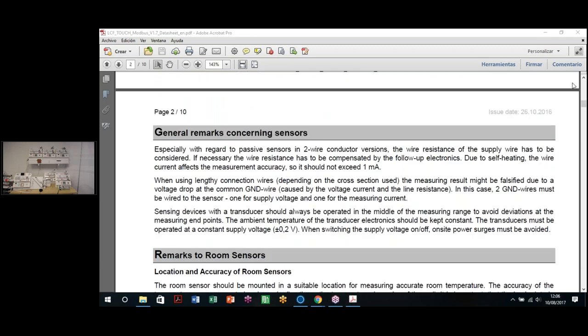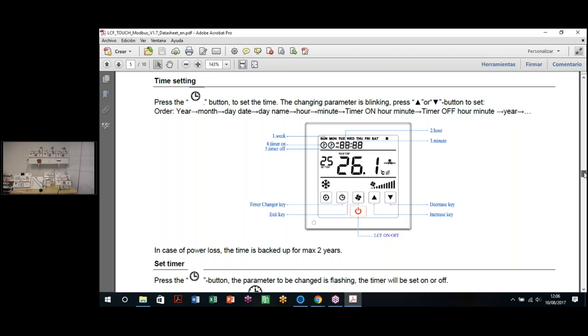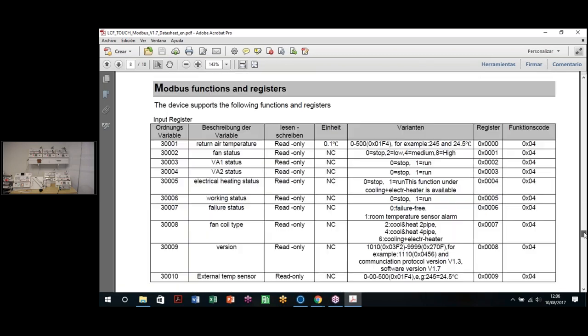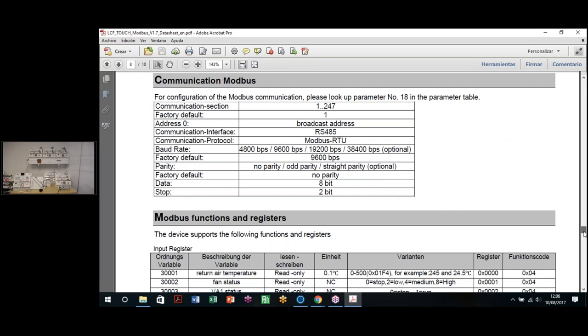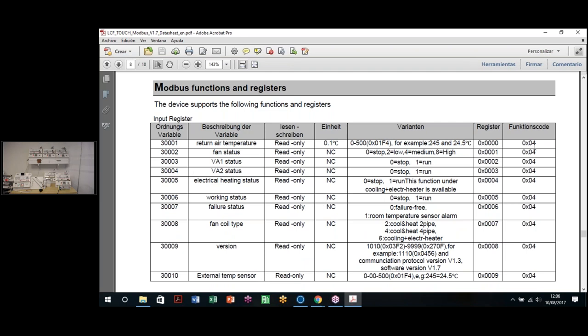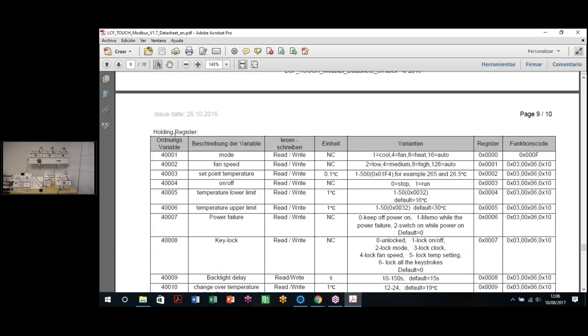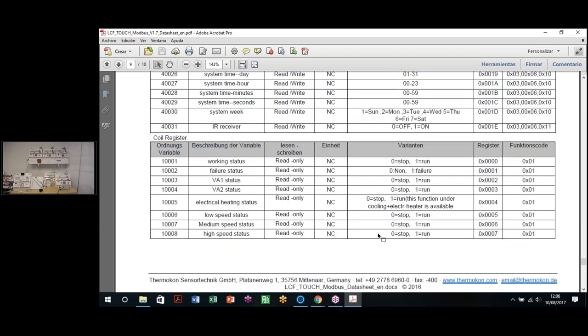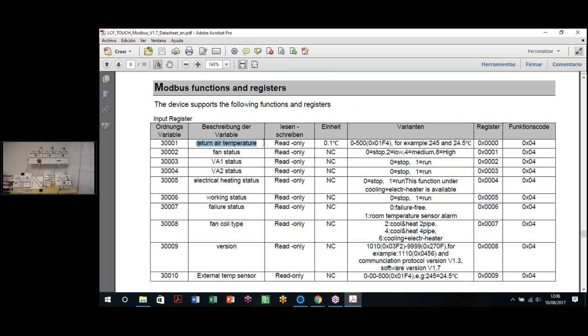Every Modbus device user manual should have a list of the registers that this device uses. In this case, if we go to the bottom, we can see the Modbus communication options, and below it a register table that shows us the configuration of each of those registers. We have input registers, holding registers, and coil or output registers. In each table, we have the name of the variable, the type, whether it's read-only, writable, or any other type of variable, the range, and most important, the address of the register, and the Modbus function that we're going to use to read or send information to this register.